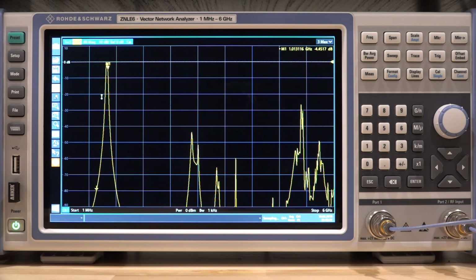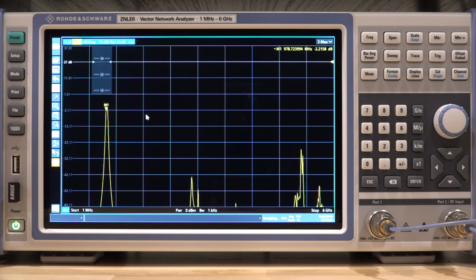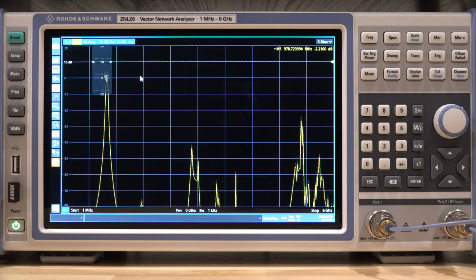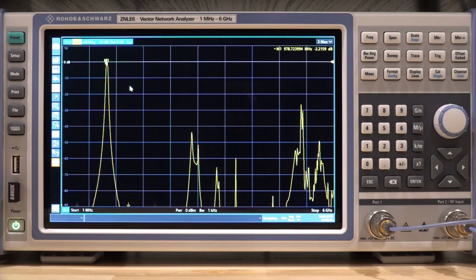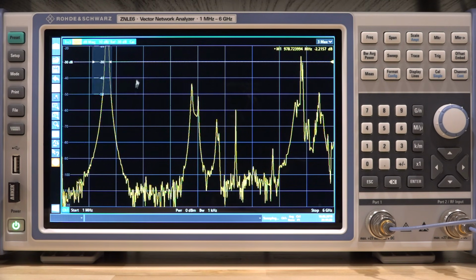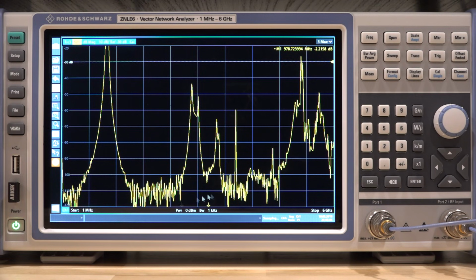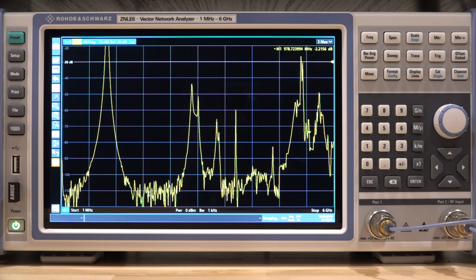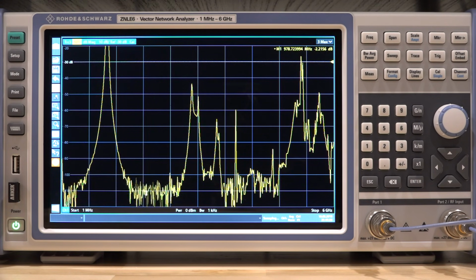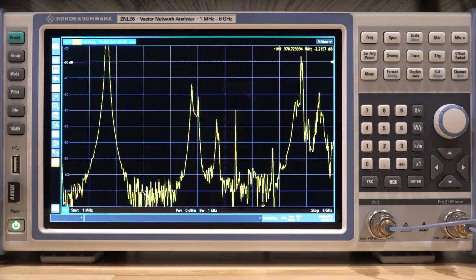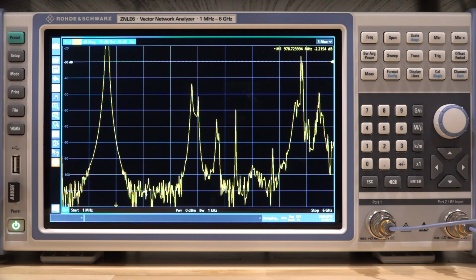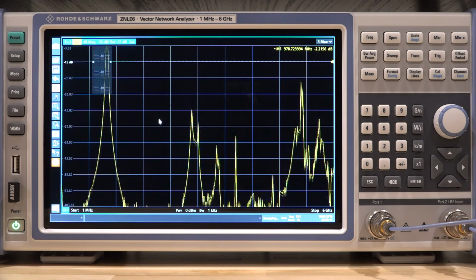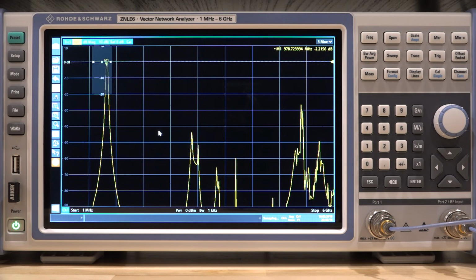Now, if I want to move the waveform up and down, it actually has a very nice graphic associated with it. So you can move it up and down there, and it latches onto 10 dB divisions at a time. It's very intuitive. I really like this little animation. Simple things like this really make a big difference. So if I move it all the way up and put the reference at -30, you can see that the noise floor and the floor of the response of the filter is sitting at around -110 dB. That's a huge dynamic range, and we're not at the highest dynamic range. We're not at the lowest IF bandwidth anyway. So let's go ahead and put this back onto our 0 dB reference there.